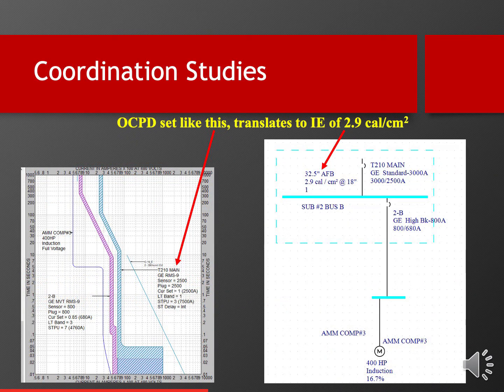Now, this is a little bit technical, but this is perhaps one of the most important parts of the presentation. What you see on the left here is what we call a time current characteristic curve, or a TCC curve. The magenta colored footprint, if you will, and the blue colored footprint are actually the time current characteristics for the various circuit breakers involved in this system. So if you look to the right, sub number 2 bus B is protected by a GE standard breaker, a 3,000 amp breaker with a 2,500 amp plug. That time current curve there, set the way it is, will calculate, as you can see, 2.9 calories of heat per square centimeter. So the incident energy is 2.9. In other words, if you were exposed to that with bare skin, you would get water blisters in your skin, but it would still be a curable burn.